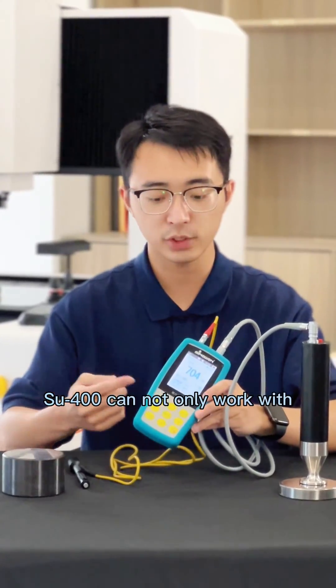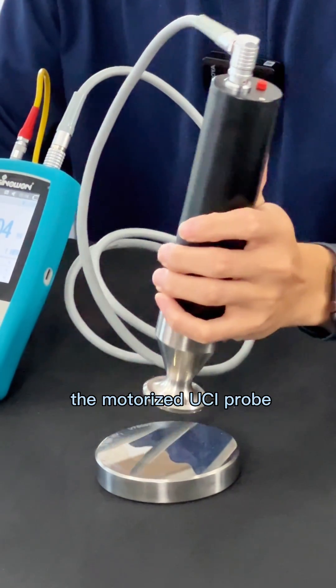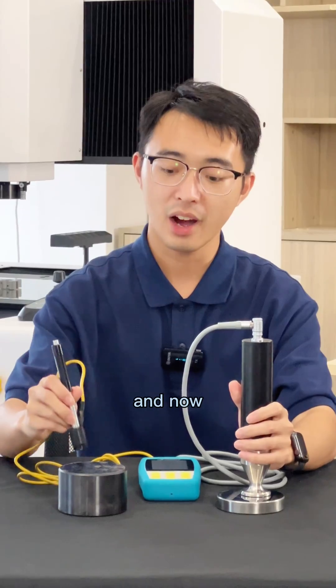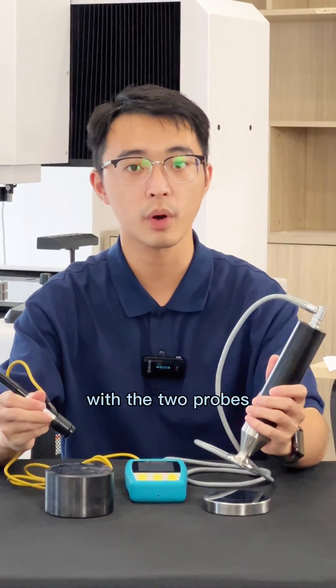As you can see, the SU-400 can not only work with the motorized UCI probe, but also the Leeb impact probe. And now we are going to test the standard blocks with the two probes.